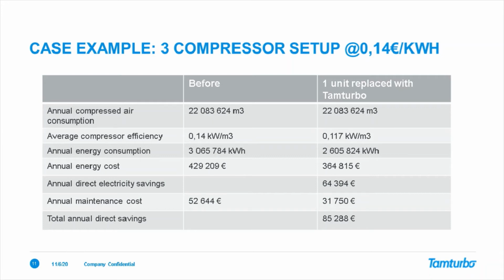Okay, the country is having a quite high electricity cost, so 14 euro cents per kilowatt hour. But even if you do it with 7 cents, there's still, I think, about 64,000 euro bottom line annual savings. So what this is saying is that the customer uses 22 million cubic meters of compressed air in a month. No, sorry, this is a year. In a year. And previously, the efficiency of the compressors was 0.14 kilowatts per cubic meter.